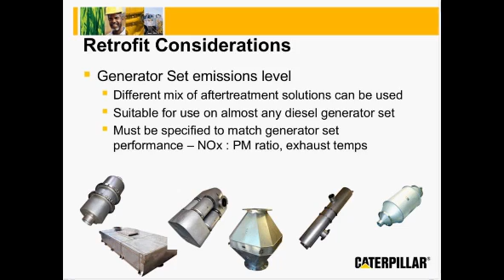There are some things to be aware of when looking at retrofits. The first is the generator set's emissions level—you need to know not only the emissions level you must meet for the installation, but also your current emissions. This allows a vendor to provide a different mix of aftertreatment solutions to meet the required levels. This mix of solutions is suitable for use with almost any diesel genset manufactured, but they need to be specifically matched to the generator set's performance. The NOx to PM ratio and exhaust temperatures are very critical in the design and specification of an aftertreatment system.